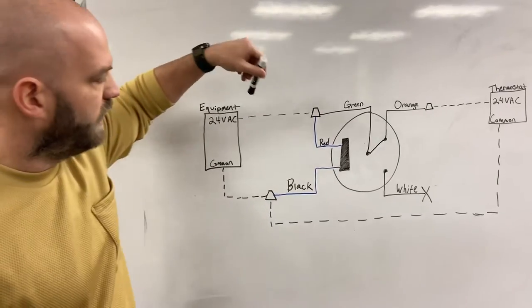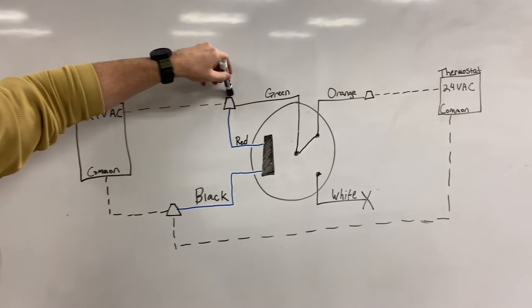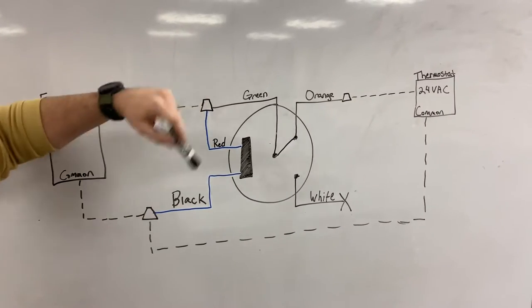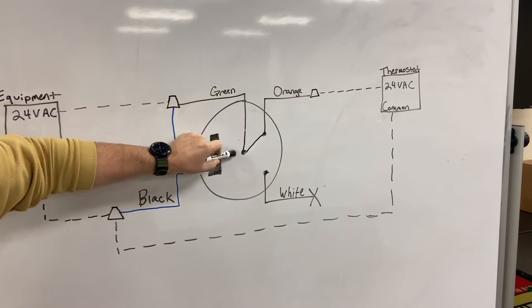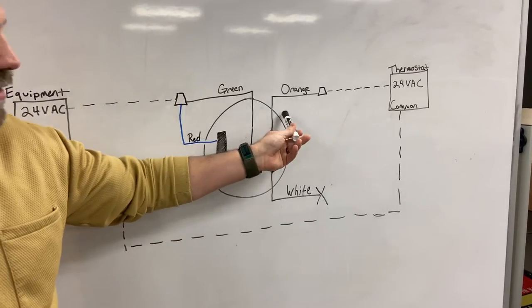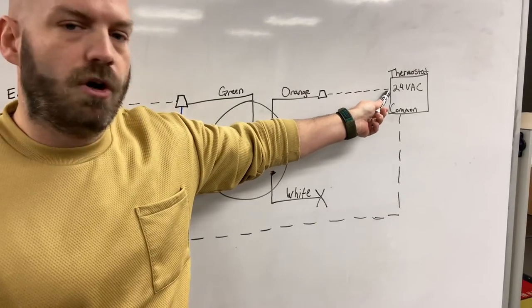So if we come in here, we're going to look at the first circuit coming off the R of the equipment. It comes through and pigtails with the red and the green, but let's follow that green. This green comes in and goes to our normally closed switch. While it's closed, it's going to allow 24 volts to go through our orange wire that's then pigtailed in to our R terminal on the thermostat.